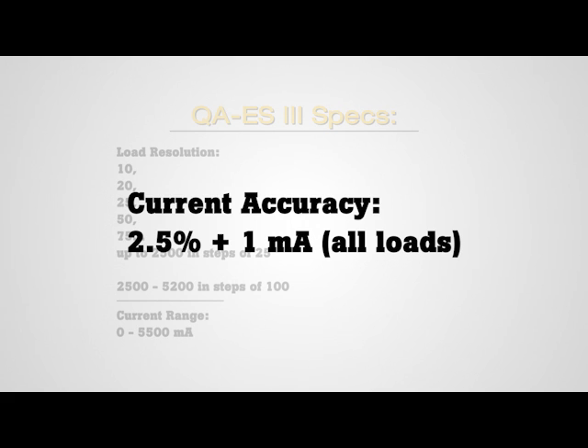Its wide range of loads allows users to test the breadth of electrosurgical generators. Notably, the QA-ES III has a 20-ohm load to support ValleyLab electrosurgical units, including the Force Triad. The QA-ES III also has double the RMS current range of its predecessor — it can measure current from 0 to 5,500 milliamps. Plus, it's twice as accurate, with current accuracy of 2.5% of reading plus 1 milliamp for all loads.